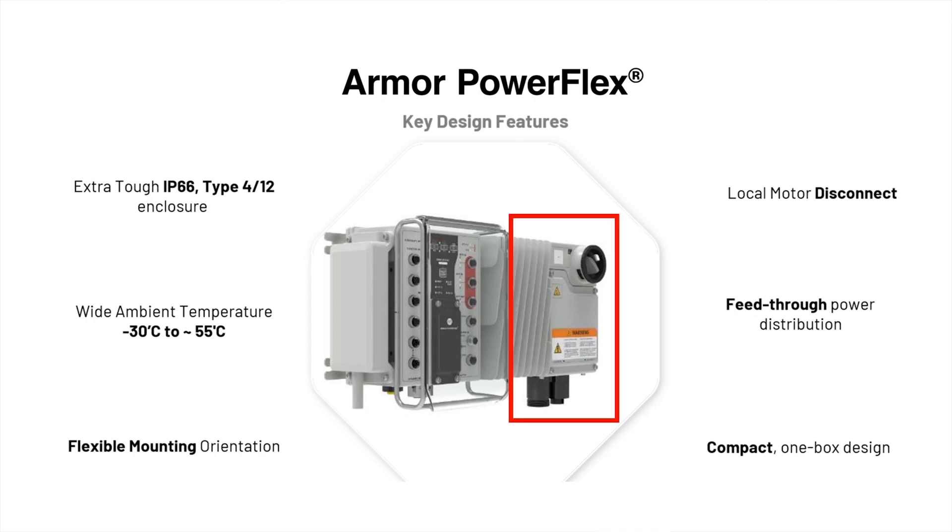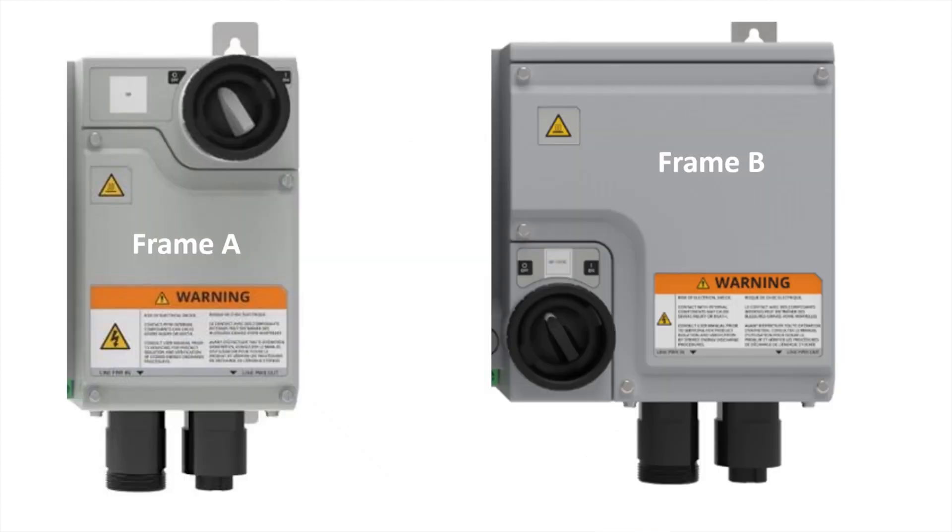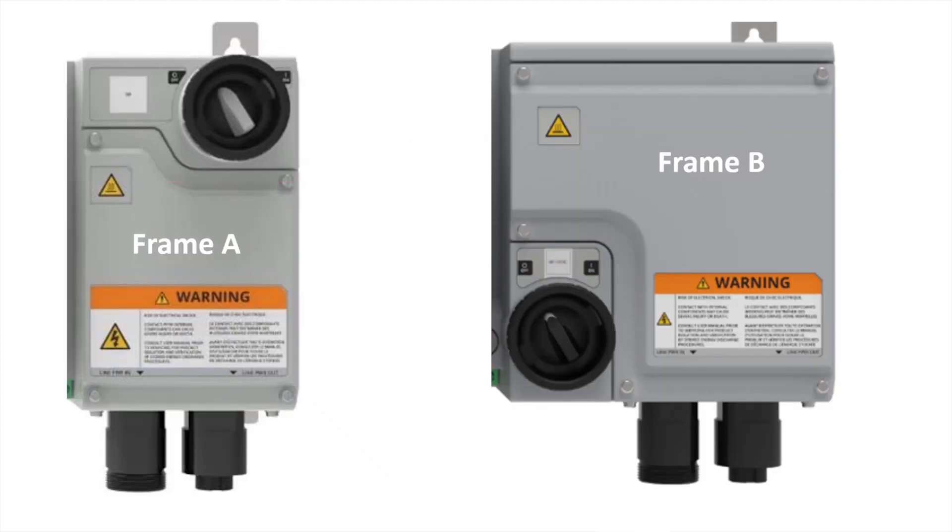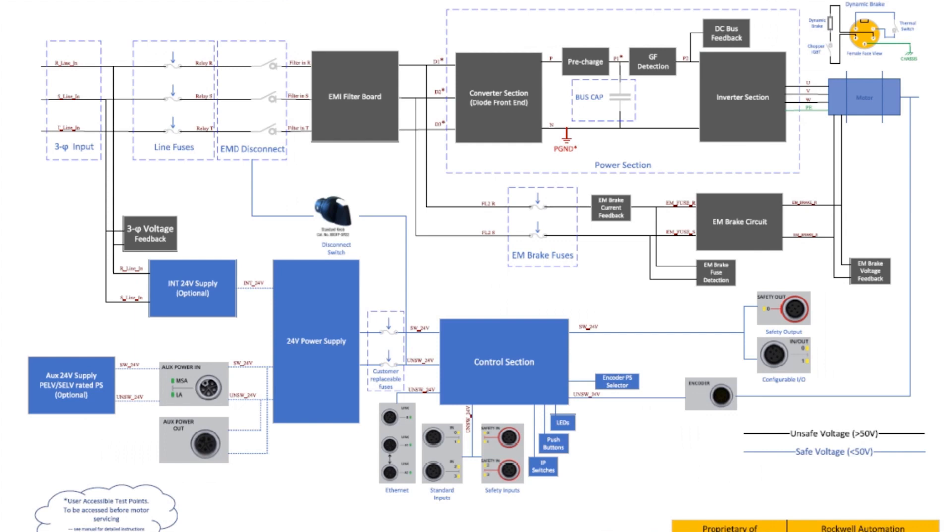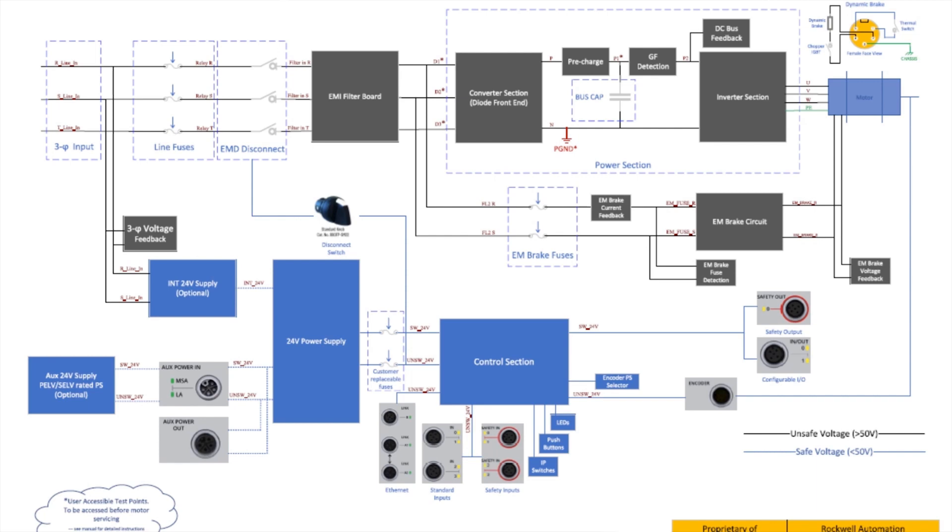When we zoom in, we can see the local lockable disconnect as well as the capability of pass-through power from the M35 three-phase power in and out connectors. The Armor PowerFlex has an optional internal power supply seen here in the wiring diagram. Using the internal power supply negates the need to have a separate 24-volt power supply somewhere else to supply the control section of the drive as well as other devices that need 24 volts near the drive.